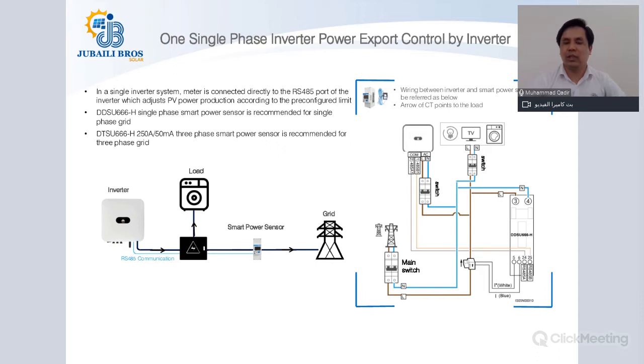And similarly, you will have a current transformer, which will also be supplied with this power sensor on the grid side, with the arrow directing towards the load side. Sometimes we have seen that the EPCs make the mistake of not caring about this arrow. The CT has a direction shown on it. You need to make sure that the direction of the CT is towards the load side, but connected on the grid side, to know whether the current is going towards the grid or coming from the grid side.